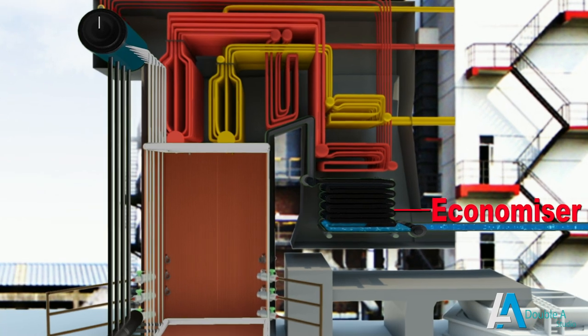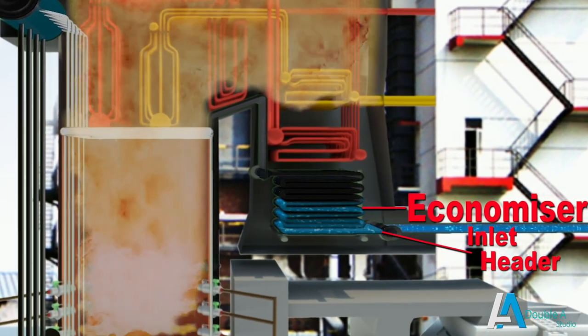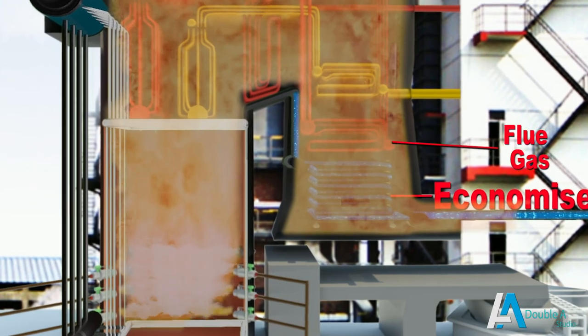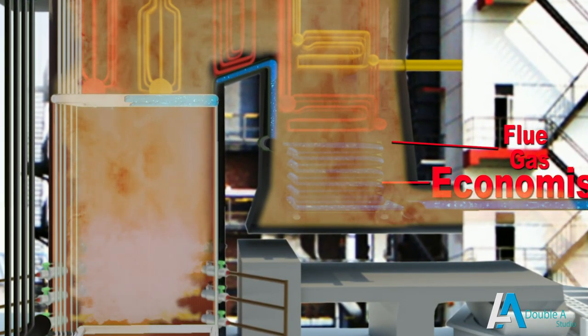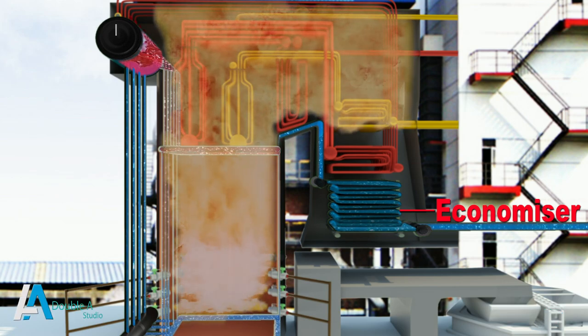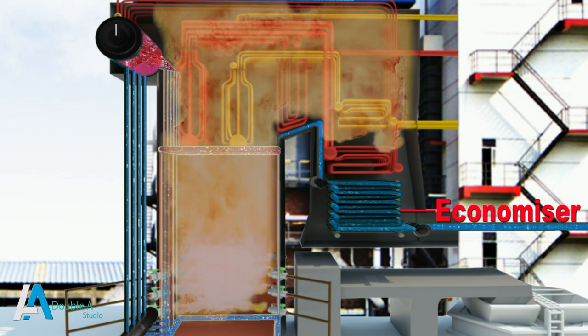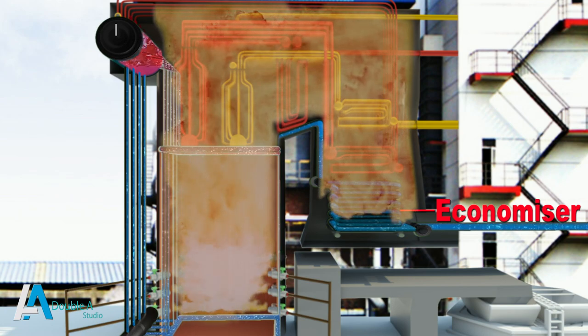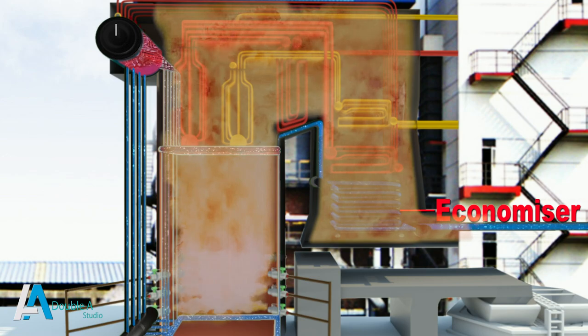Feed water enters through the inlet header and passes through the coiled path of the economizer. Hot flue gases pass across these tubes and increase the temperature of feed water inside the economizer tubes. The coiled structure of tubes increases surface area and contributes to optimum heat transfer. The heat thus gained increases the sensible heat of feed water before entering the boiler, thereby reducing fuel consumption for producing steam.